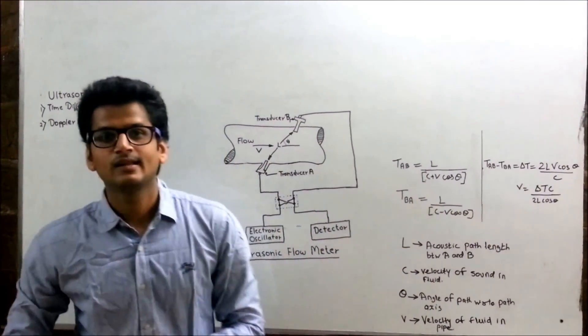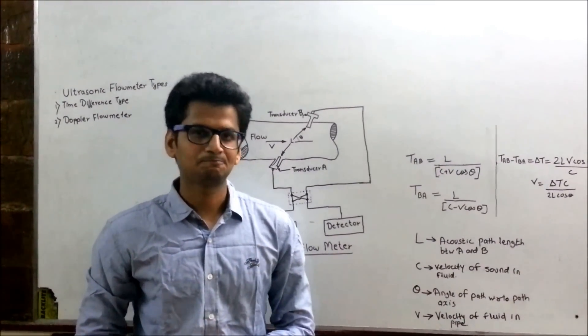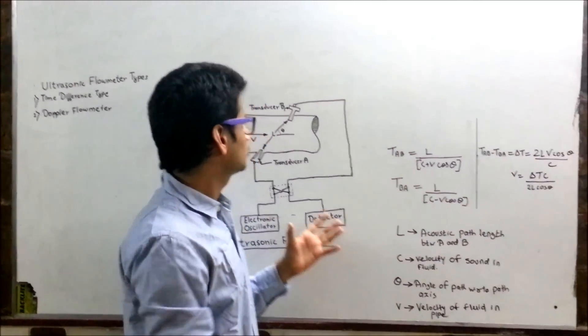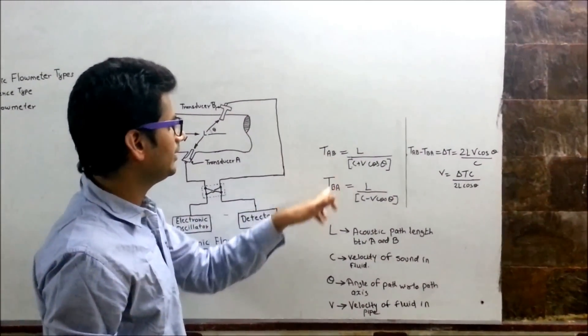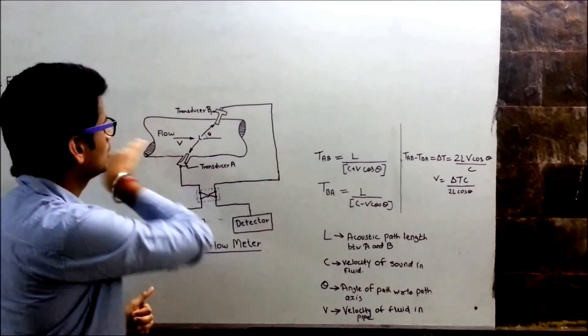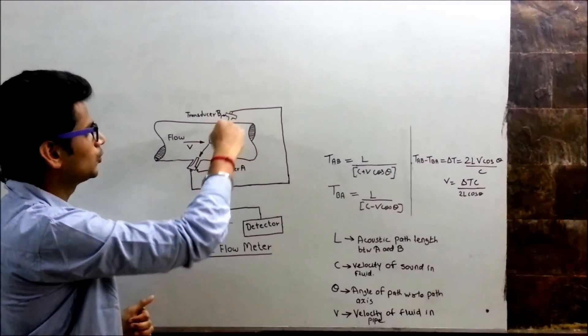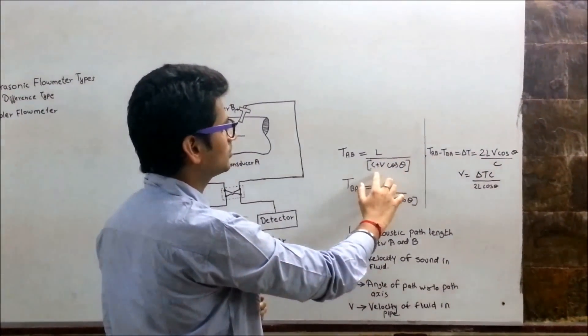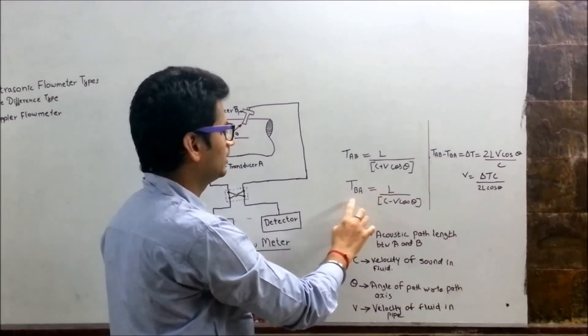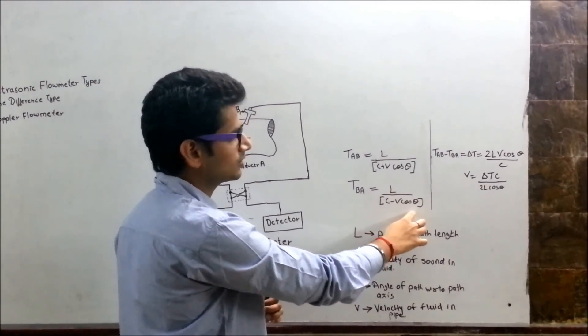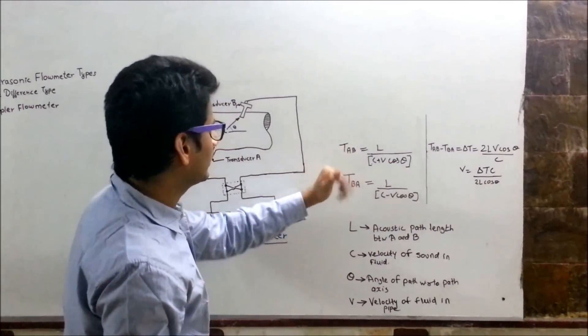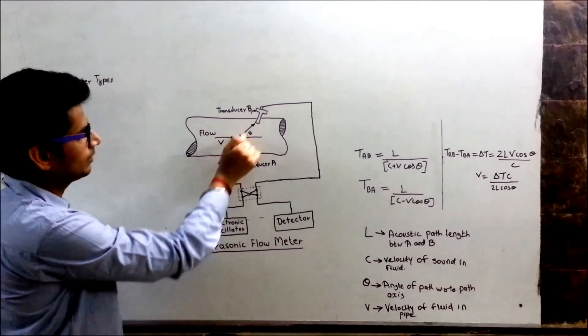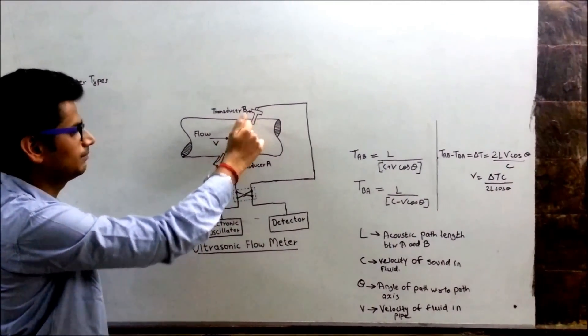As I mentioned earlier, it is based on time difference type, so there has to be some formula. The formula is TAB and TBA - that is the time taken for the fluid to pass from A to B and B to A. TAB is L upon C plus V cos theta and TBA is L upon C minus V cos theta, where L is acoustic path. Acoustic path means this path, which you can see, is acoustic path.